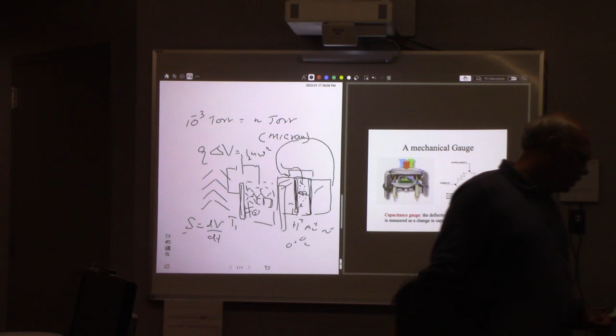In mechanical gauges, they basically apply some current, then they have this Wheatstone bridge. So if your system is pumping out, maybe your resistance changes, and that can be measured by measuring the output voltage. That's something simple, any parameter that changes, like the thermocouple gauge, or the mechanical one.